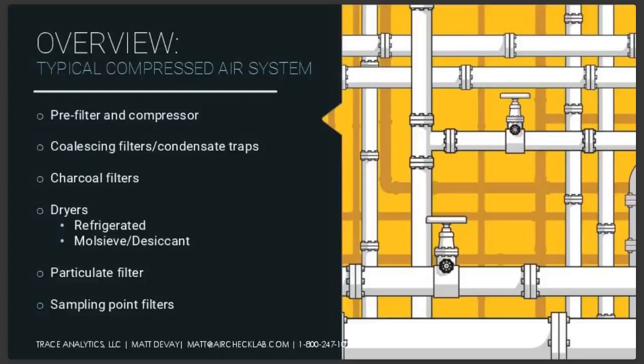And then finally the air ends up at the point of use. And at your point of use, you might have quite a bit more filtration. Another desiccant filter to remove water, a condensate filter to remove oil and water, and then almost always some kind of extra particulate filtration as well.